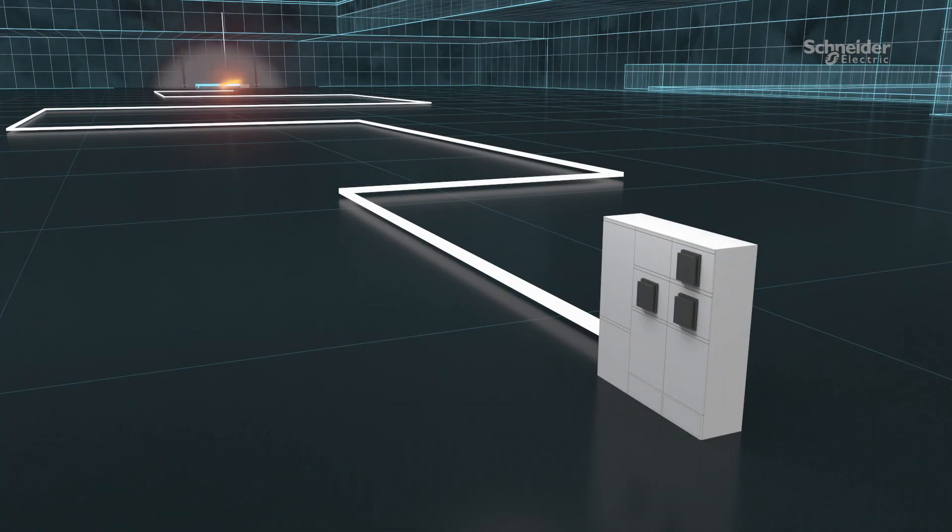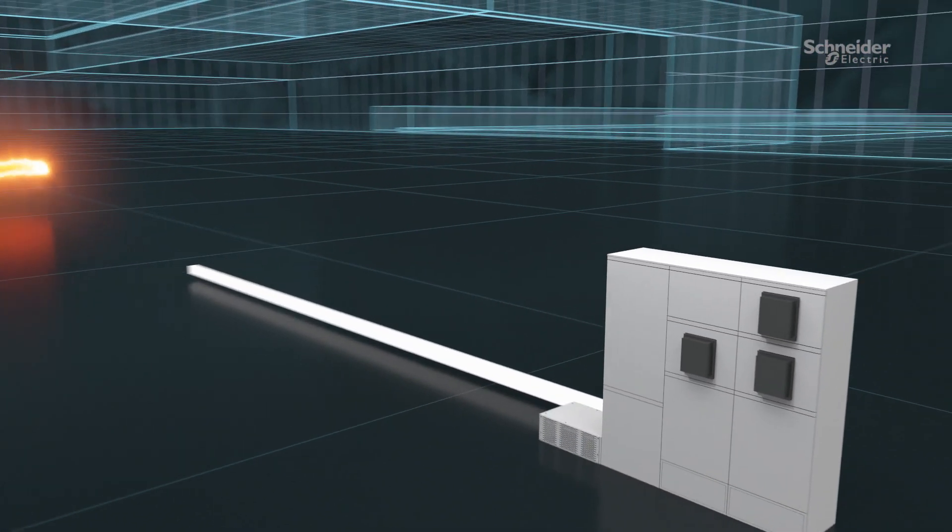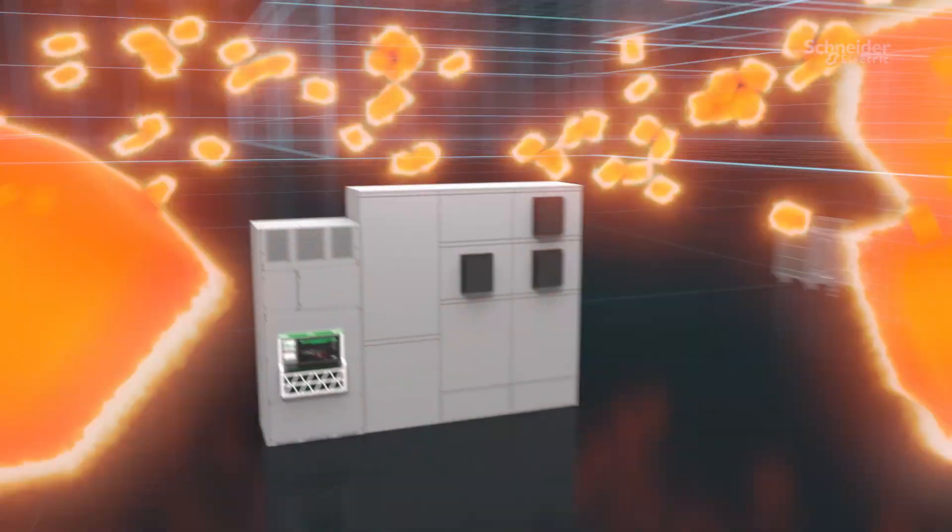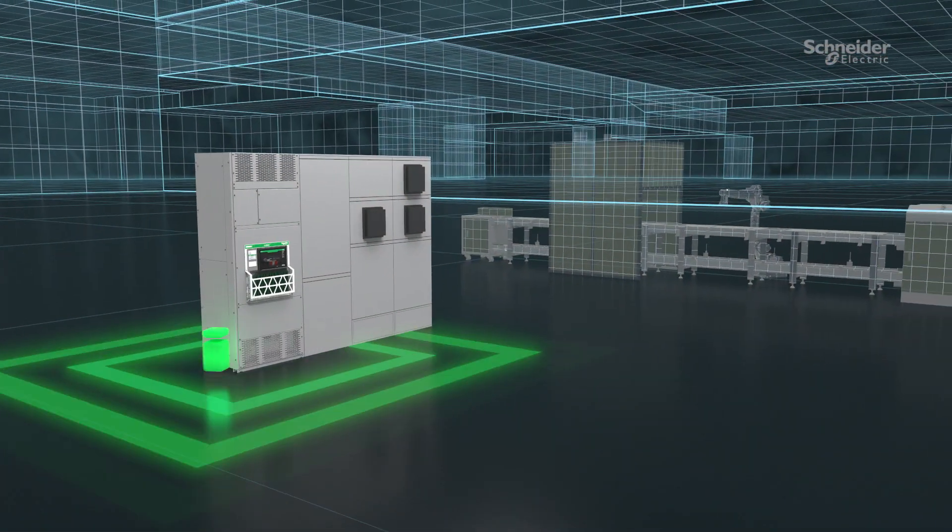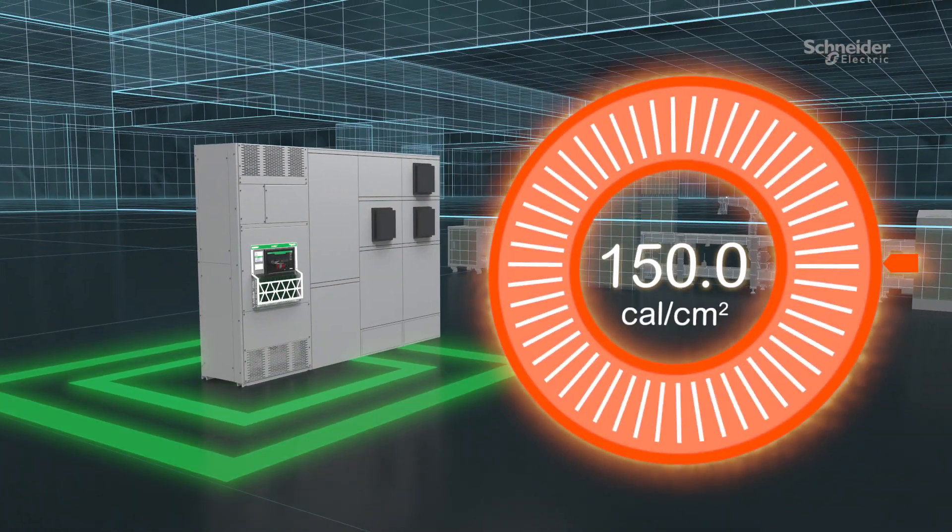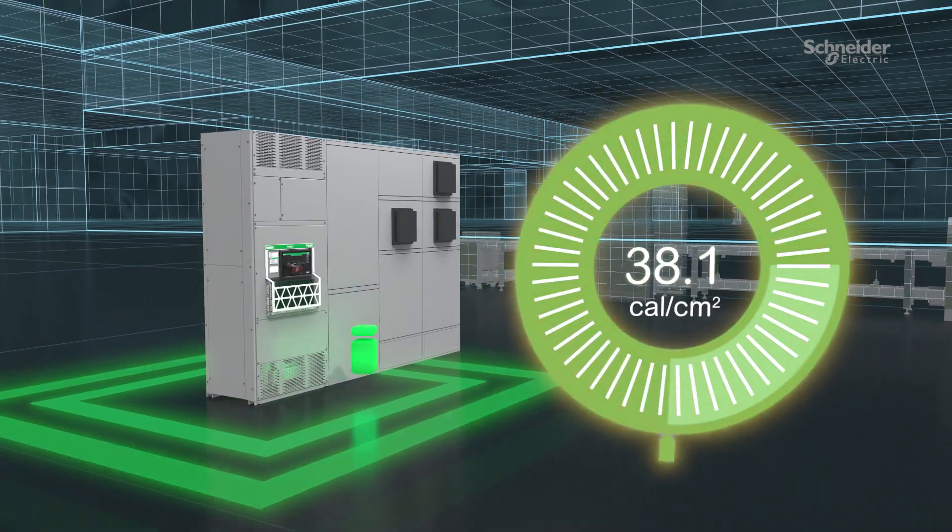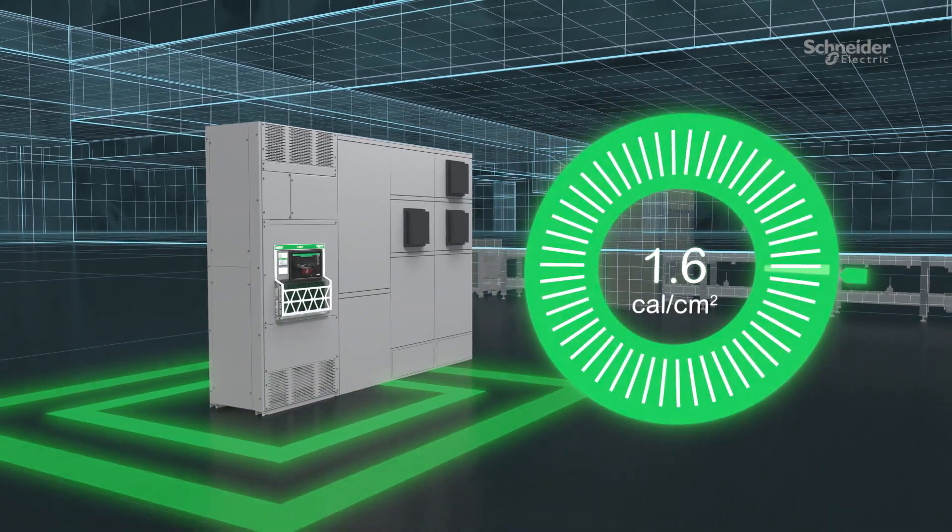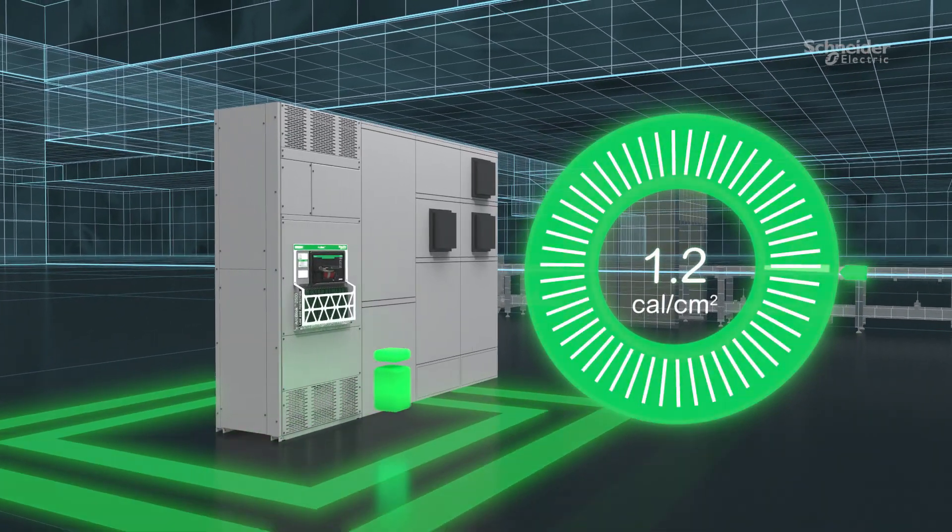ArcBlock addresses this line side dilemma by isolating the incoming circuit breaker, reducing line side energy measurements from numbers such as 150 calories per square centimeter down to 1.2 calories per square centimeter.